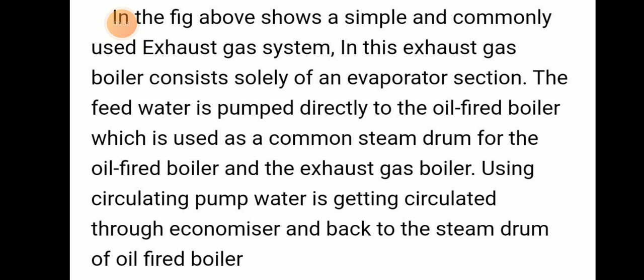The figure above shows a simple and commonly used exhaust gas system. The exhaust gas boiler consists solely of an evaporator section. The feed water is pumped directly into the oil-fired boiler, which is used as a common steam drum for both the oil-fired and exhaust gas boiler.